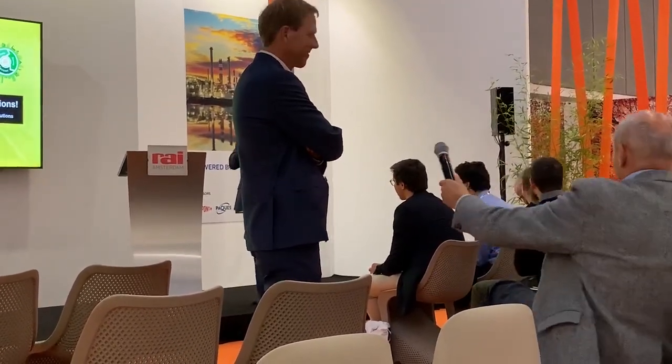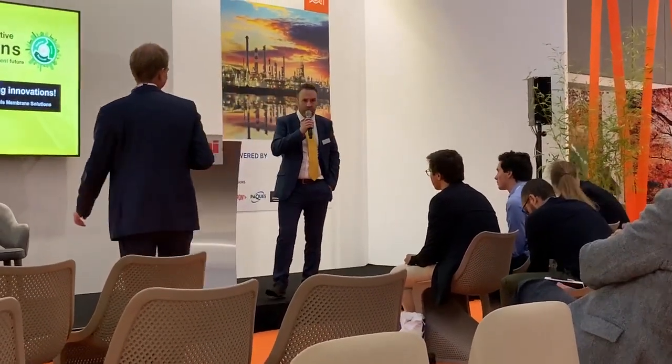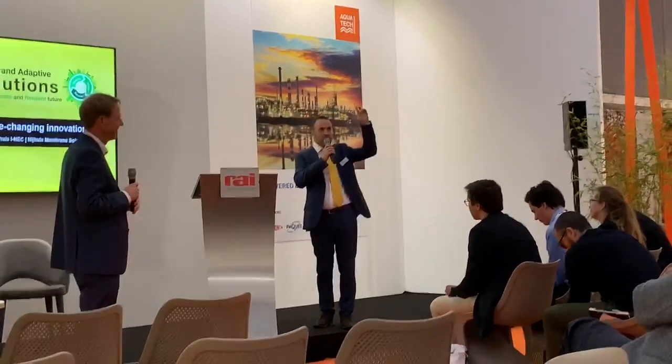It's an excellent question, and it's what I was very fearful of on starting this trial, because I thought by introducing this to the system we'd have foam coming out of the top of the cooling towers and whatnot. So yes, we did have an antifoam on standby, but we started off. The dose rate of this product is very, very small. We're looking at between the 1 to 5 ppm range. And we started off very low, just to make sure we didn't have any foaming issues.